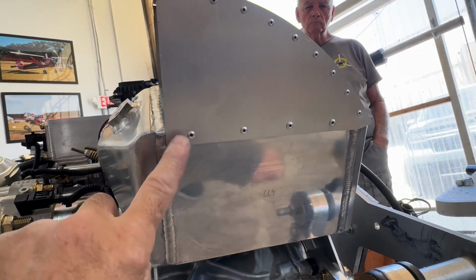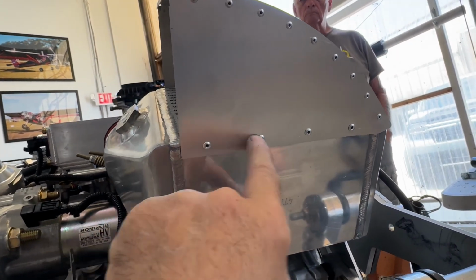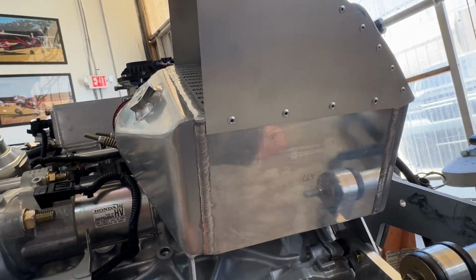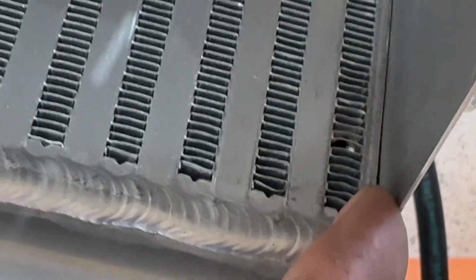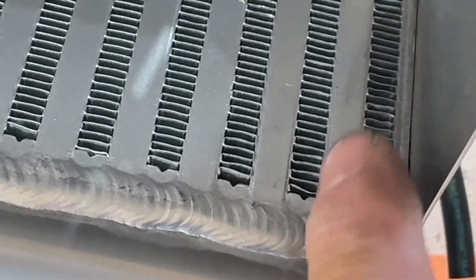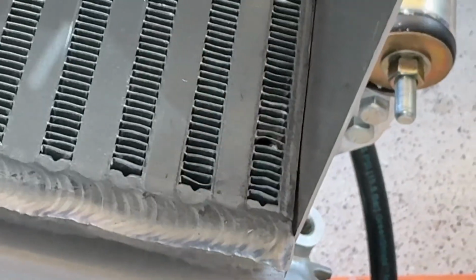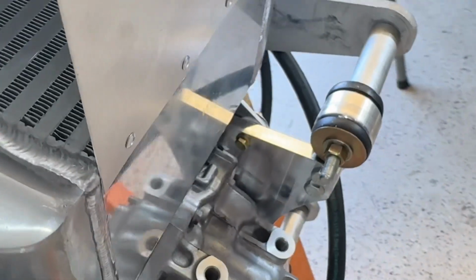When you drill these holes, use the 5/32 rivets, or number 5. Make sure you don't drill too deep. You can drill through this first plate, there's no issue, and you can drill into these fins, but you don't want to drill into this tank because you'll get an air leak. The rivets end up inside there, so you just push on the rivets when you pull them.